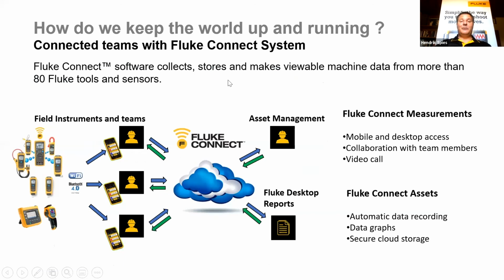Last but not least, guys, it excites me a lot, the connected teams of Fluke Connect system. So how does this work? We've got the Fluke Connect platform that collects, stores, and makes viewable machine data for more than 80 Fluke tools and sensors in the field. So if you have a look here, we've got our field instruments and teams. Then we've got the asset management team sitting in a centralized location or an office. And then we've got the Fluke desktop reports, maybe some technicians or people that need to generate reports. So how does this work? Number one, you've got the Fluke Connect enabled tool in the field, which can be our multimeter clamp meter range. Most of our tools can be power quality, it can be thermal imager. We then connect via Wi-Fi, typically Wi-Fi to the thermal imager, Bluetooth to the actual hand tools themselves, or standard installation tools, and also Wi-Fi to some of our power quality analyzers and some of the other tools as well.